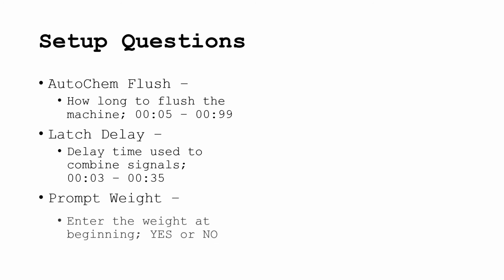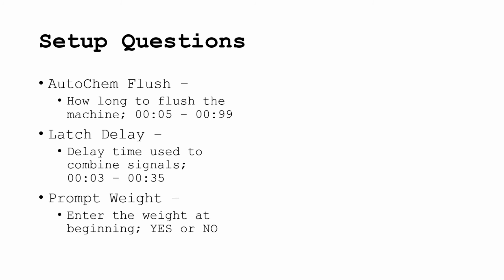Prompt Weight allows an operator to enter the weight at the beginning of the formula for reporting or ratiometric chemical addition purposes. Recommended yes or no. Chemical watchdog tells how long the system will wait to alarm if the machine does not answer the chemical request in the specified time. Recommended range 0 to 99 minutes. Signal mute time, this is the amount of time that the alarm will be silenced by pressing the CLR button. Recommended range 0 to 5 minutes.